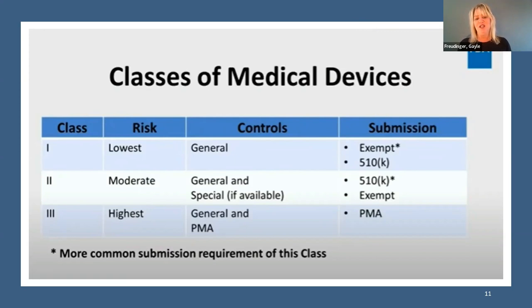Class three devices usually sustain or support life. They're possibly implanted or present some potential unreasonable risk of illness or injury. So about 10% of medical devices fall under this category. Vascular stents are class three devices and require pre-market approval. Approval is usually obtained through the submission of what we call a pre-market approval application, and we'll go through that later on. Other examples of class three devices include implantable pacemakers and breast implants.